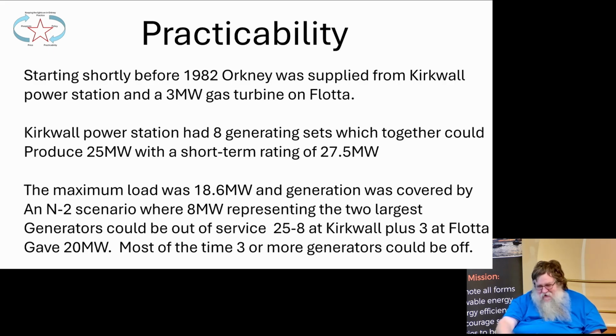Starting shortly before 1982, Orkney was supplied from Kirkwall Power Station and a 3 megawatt gas turbine on Flotta. So we'd got 8 generating sets in Kirkwall, which could produce 25 megawatts, short-term rating of 27.5. The maximum load was 18.6 megawatts, and generation was covered by an N-2 scenario where 8 megawatts represented the 2 largest generators could be out of service. So 25 minus 8 at Kirkwall plus 3 at Flotta gave 20, which is above the load of 18.6. So it met the requirements.